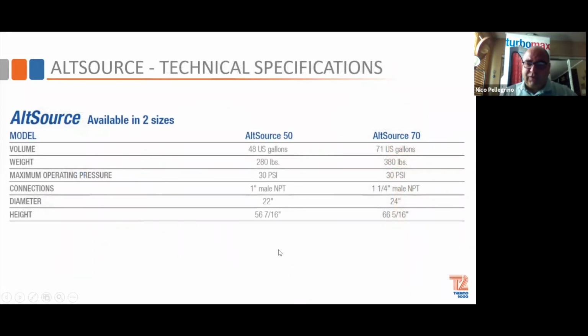Again, the alt source comes in two sizes, 50 and 70. I know there's a lot of guys saying, what's the difference between this and the Combo Max? If you notice, this does not have all the components on top of the tank. So you need your fill valve, you need all that stuff exterior added onto the system as opposed to the Combo Max. Because in some cases, if you're using it without domestic production, you don't need all that fancy stuff on top of the tank.